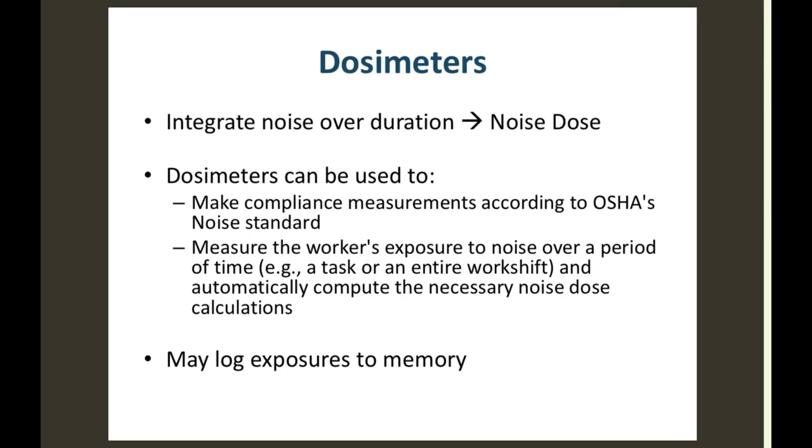So what are the settings I want to put this on if I'm going to do worker exposures? First of all, what's the first thing I want to do? Make sure your battery's full. Yeah, make sure the battery's full. How about calibrate again, right? Calibrate is the first thing we want to do. Second, make sure the battery's full. How about the third thing? What setting?